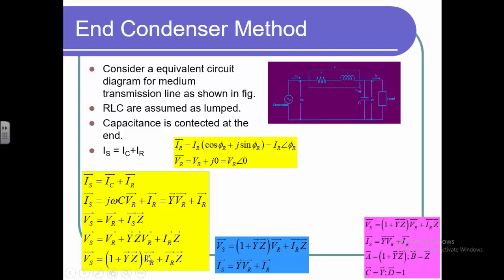Now equating these two equations with the ABCD parameter format, the ABCD parameters for the end condenser method are: A = 1 + YZ, B = Z, C = Y, and D = 1. By simply remembering these four parameters, we can write the equations for VS and IS for the end condenser method.